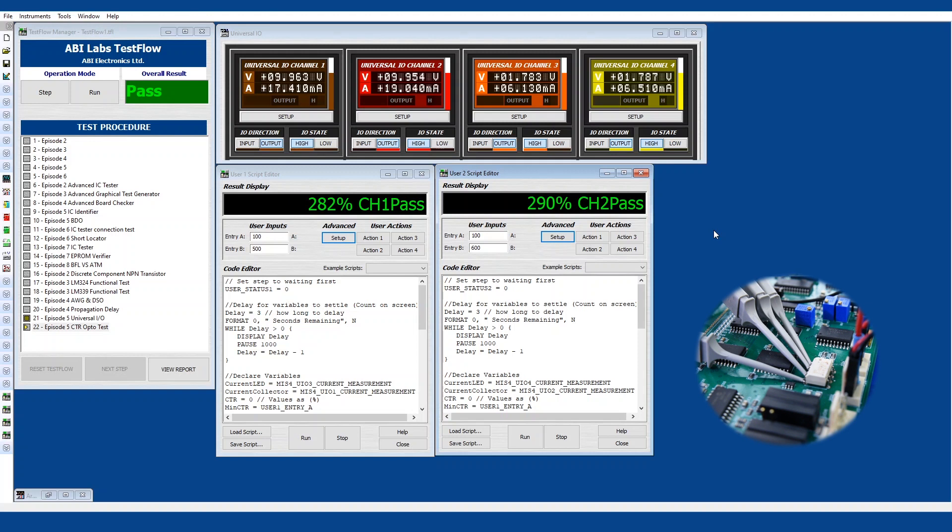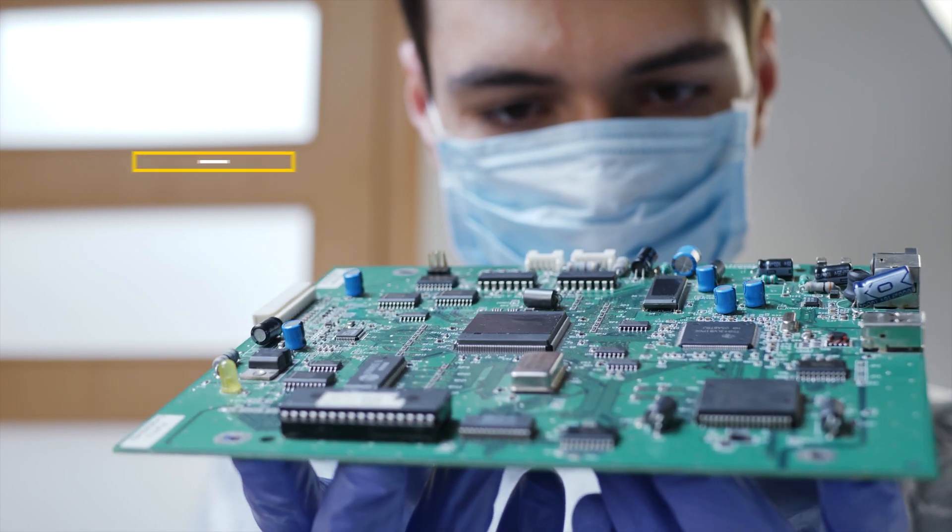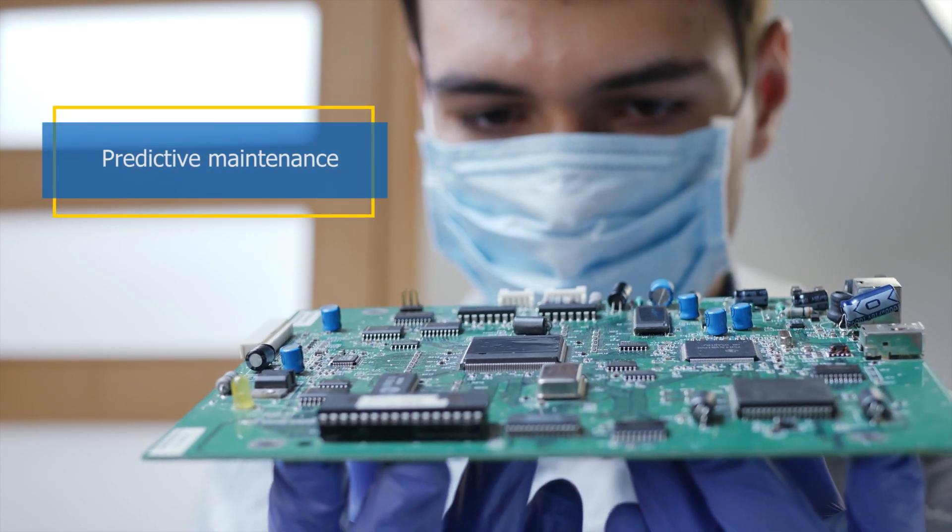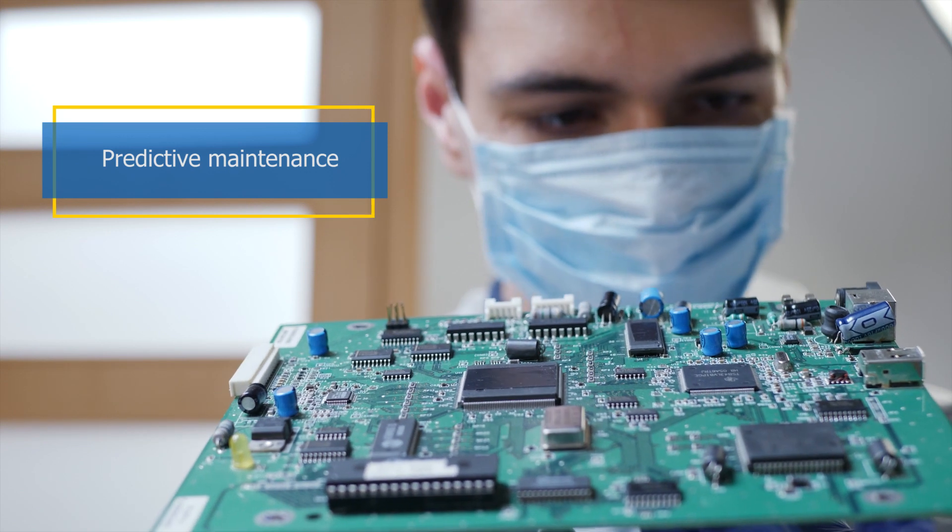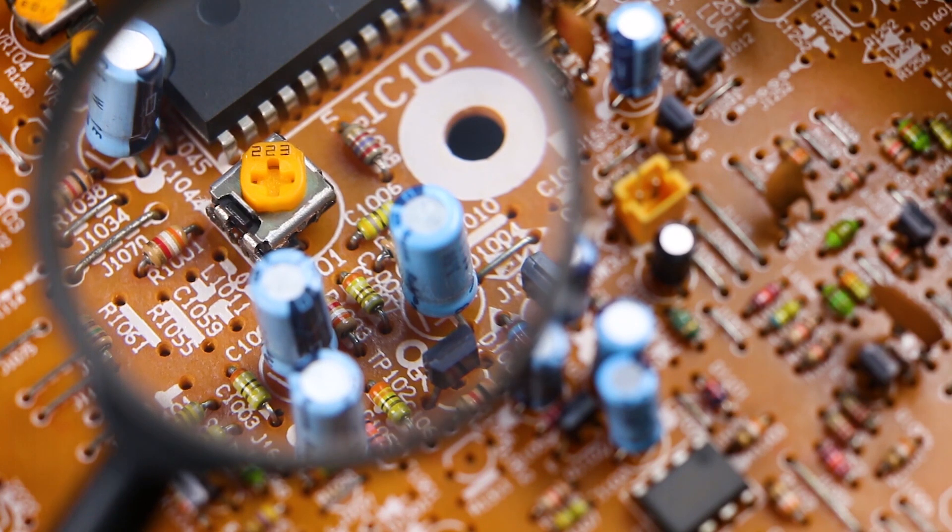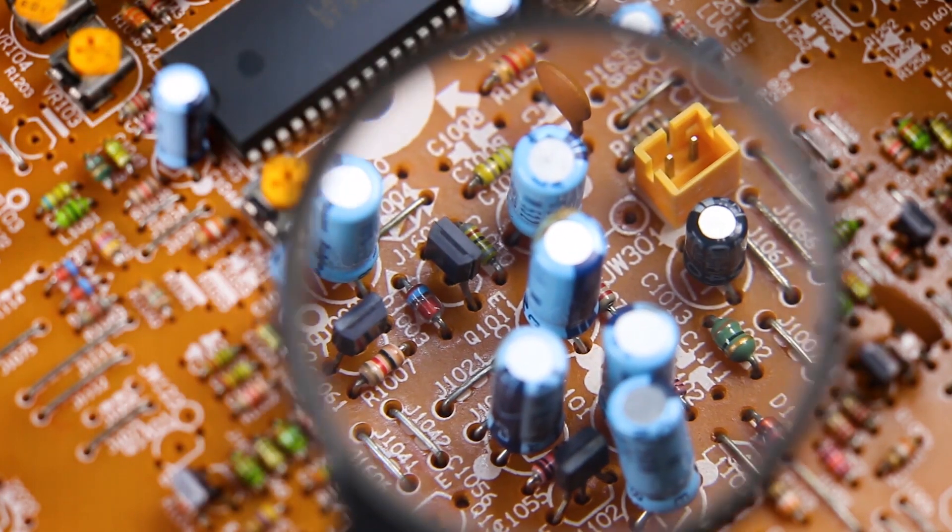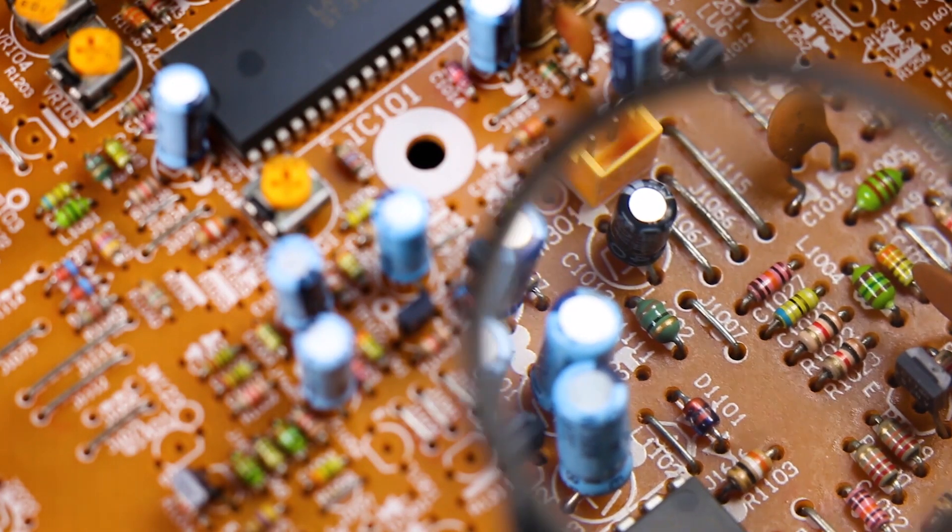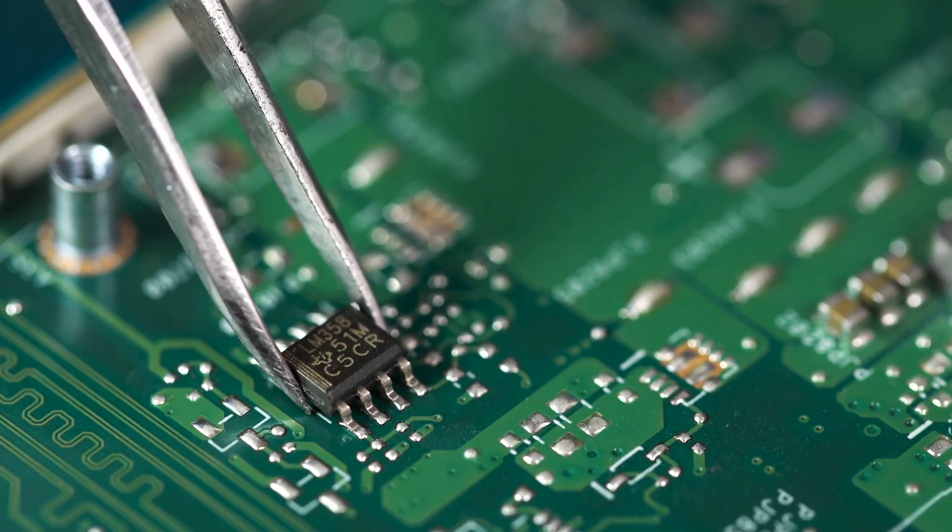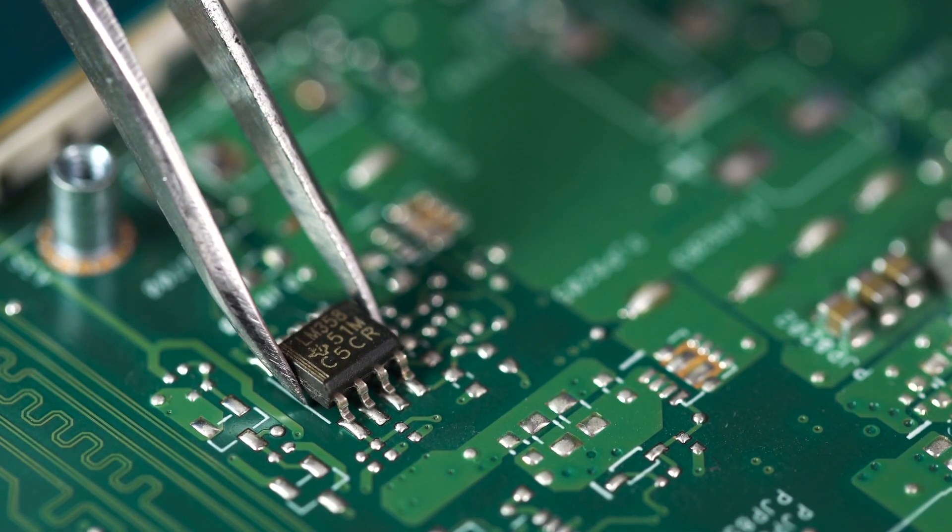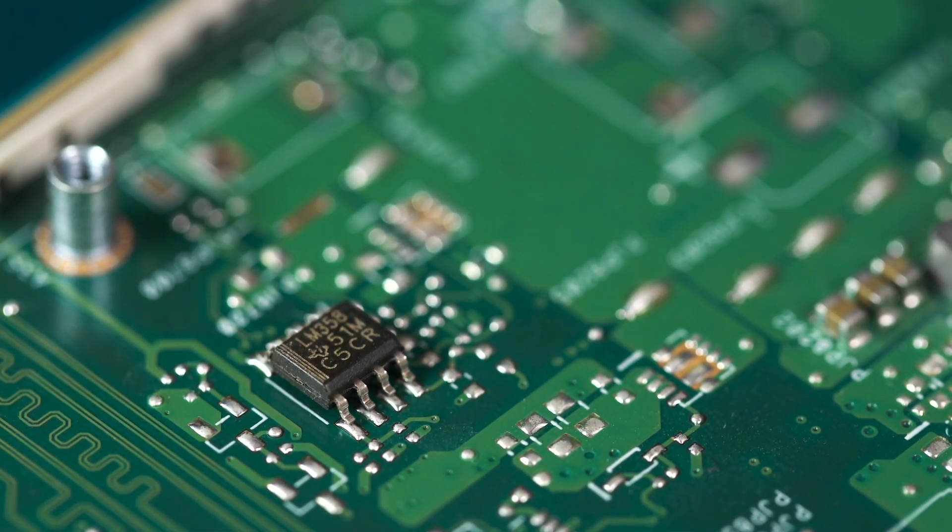So that's really useful for predictive maintenance because what we can do is test our component and see how it's operating and whether it is degrading slowly. This will allow us by monitoring the propagation delay as well as the CTR to see whether our component is coming to the end of its life and then obviously we can in time replace the component if necessary.